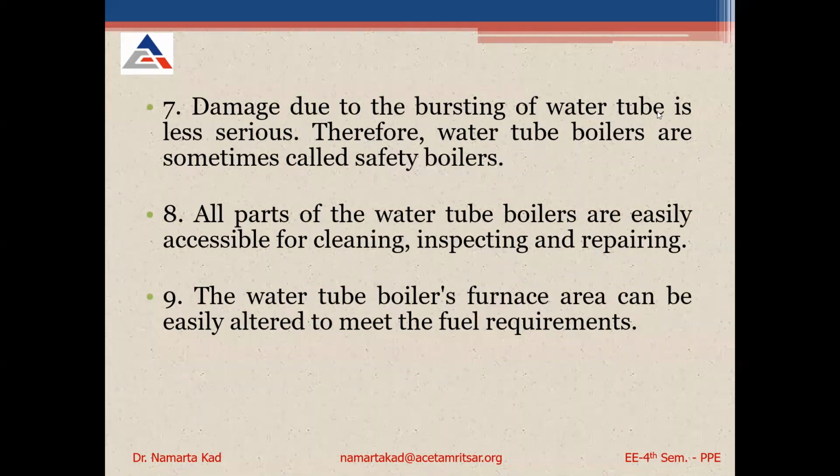Damage due to the bursting of a water tube is less serious. Therefore, the water tube boilers are sometimes called safety boilers. ठीक है, अगर tubes damage हो जाती हैं तो जो इससे डैमेज क्रिएट होता है वाटर ट्यूब बॉयलर से वो कम है एज कंपेयर टू द फायर ट्यूब बॉयलर्स. All parts of the water tube boilers are easily accessible for cleaning, inspecting and repairing. तो easy है इस केस में cleaning, repairing. Water tube boiler furnace area can be easily altered to meet the fuel requirements. Alteration की जा सकती है as per our fuel requirements.